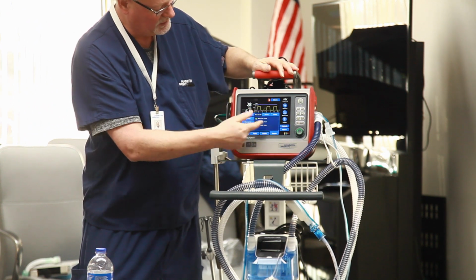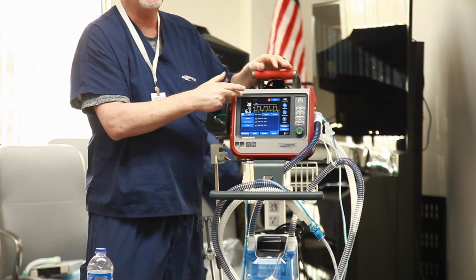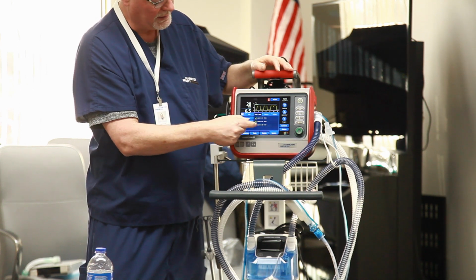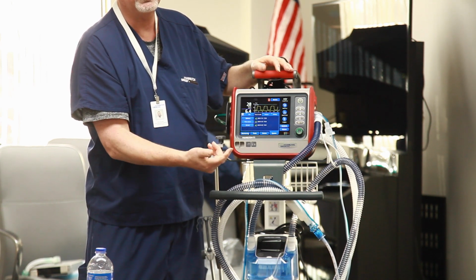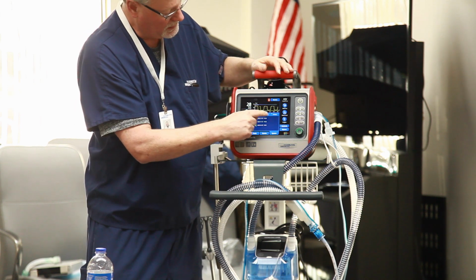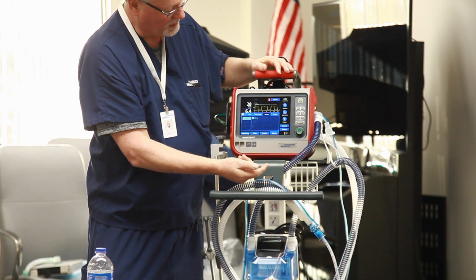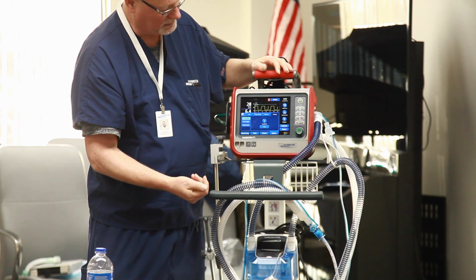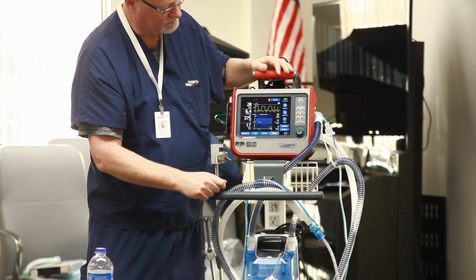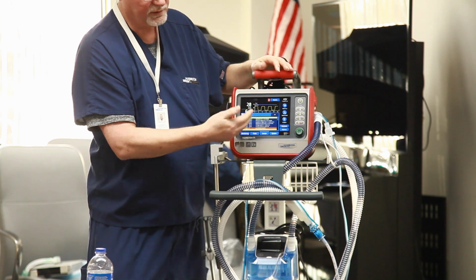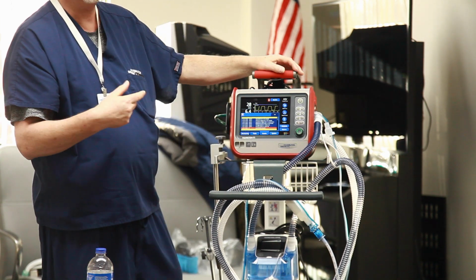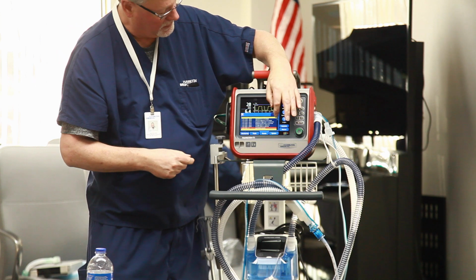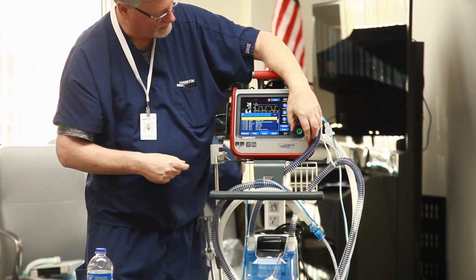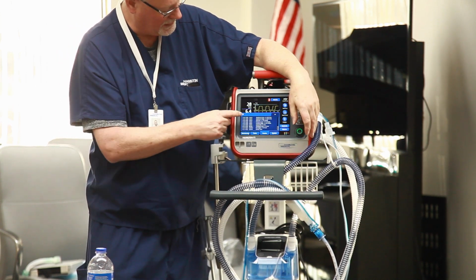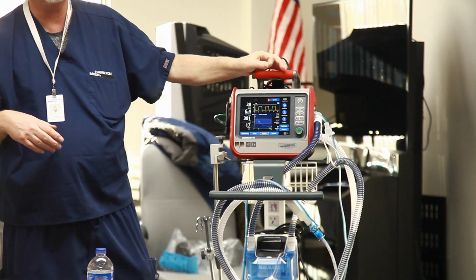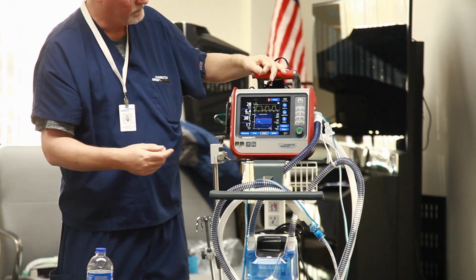Tests and calibrations would be, let's say it gave me an alarm, calibrate O2 sensor. You go to the tests and calibrations, you see a red X there, just push O2 sensor and it's going to calibrate. O2 sensors are always defaulted on, and then your settings for how loud it is, the date and time, and things like that. Events are just all the events for this patient. That means ventilator changes, alarms, anything like that. If I want to scroll down, I can scroll down like that. It saves up to 1,000 events per patient. Once you start a new patient on here, it's going to start all over again.